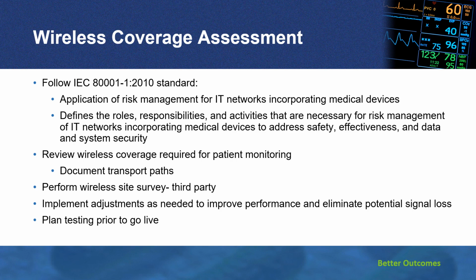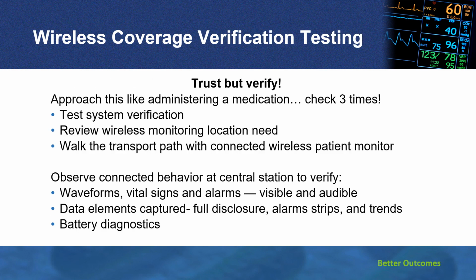And of course, before you go on any type of trip and you're doing any type of assessment, you need to do some testing. So plan to do that testing maybe more than once prior to your actual go live of using your wireless system or implementing your patient monitoring system. Like I said in the last slide, trust but verify. I think you can't go wrong by always trusting and verifying. So approach it like you're administering a medication. Check 3 times. You want to check that this test system was verified. When you did the test, everything was good. Then review the wireless monitoring locations again.